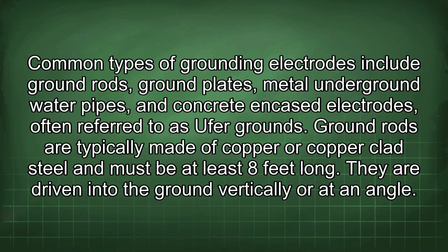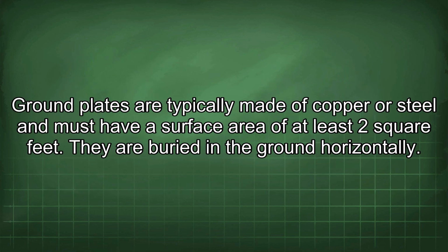Common types of grounding electrodes include ground rods, ground plates, metal underground water pipes, and concrete encased electrodes, often referred to as Ufer grounds. Ground rods are typically made of copper or copper-clad steel and must be at least 8 feet long. They are driven into the ground vertically or at an angle. Ground plates are typically made of copper or steel and must have a surface area of at least 2 square feet. They are buried in the ground horizontally.